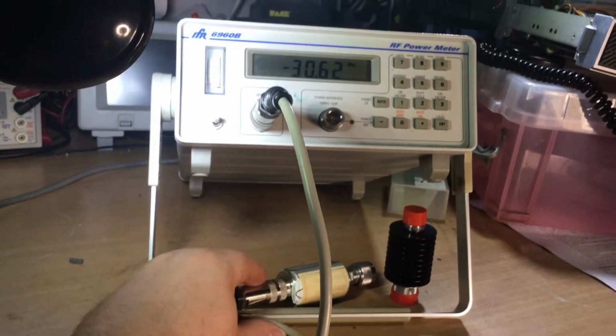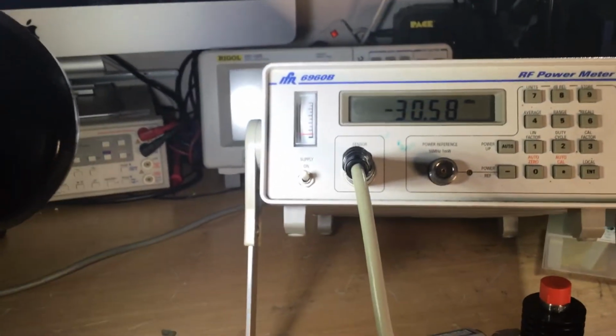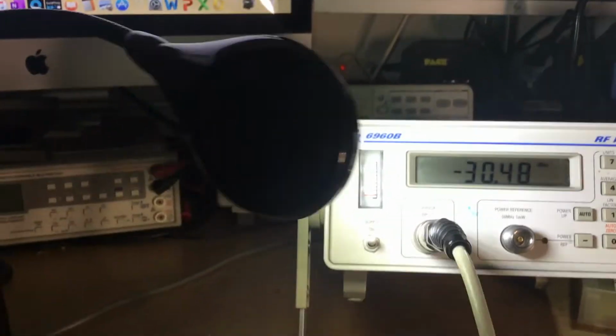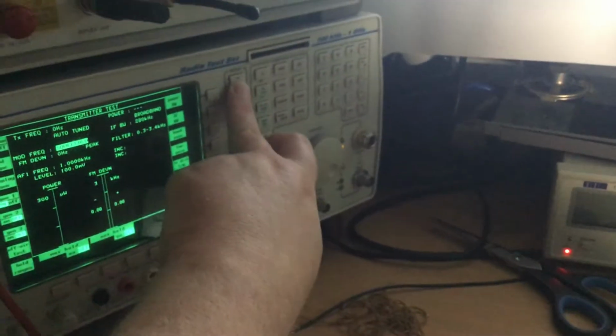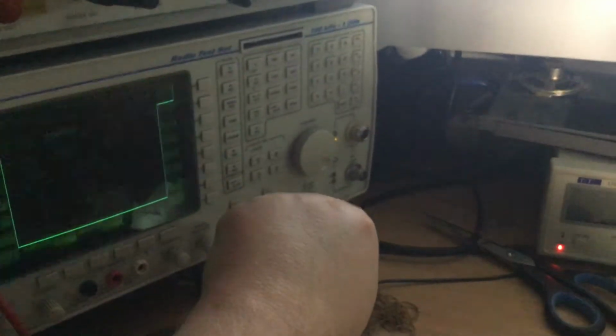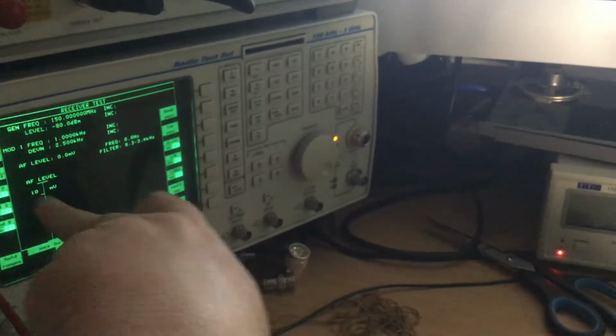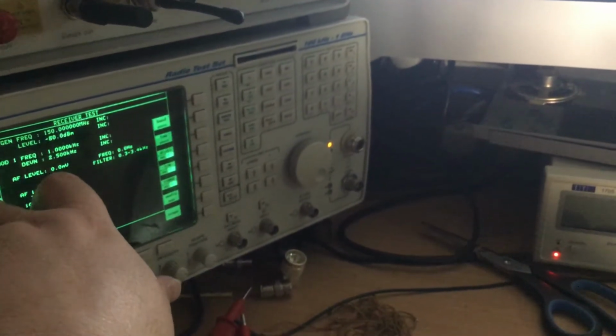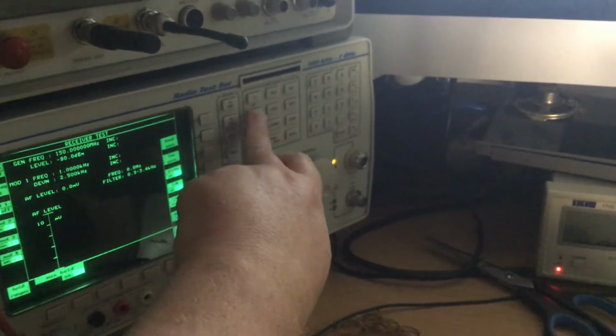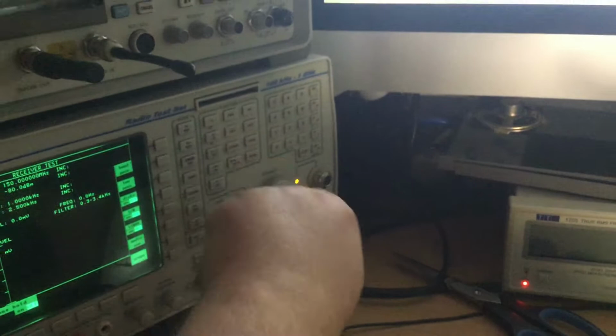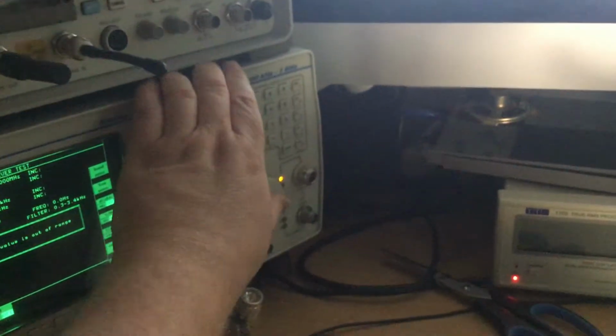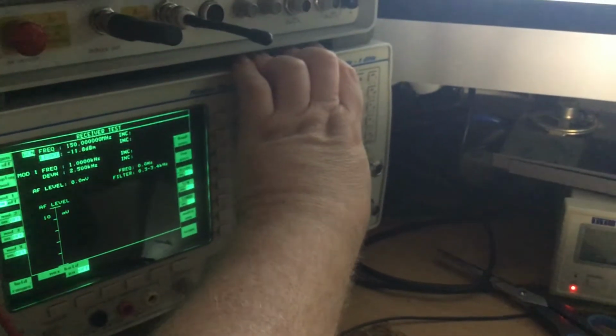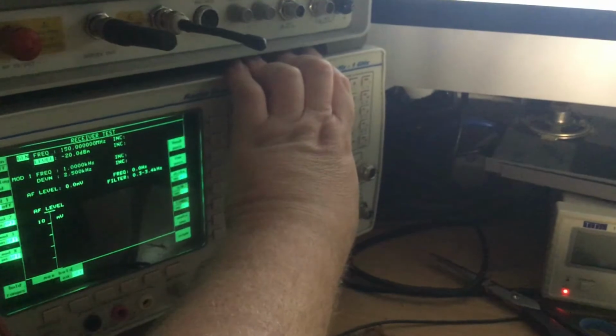So what I've done, I've set up an experiment just as an example of what we can use this with. We've got a signal generator set up, and I'm going to demonstrate it by connecting it to this signal generator here under RX test. Get it on the right screen, and then I can select a frequency, whatever it is, and the RF gen level, say 0 dBm, or if it won't go to it, in this particular case we'll go to minus 20 dBm, and then we'll see just how accurate the output of the signal generator is.